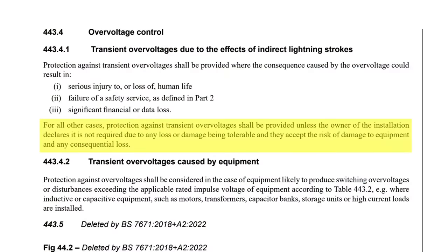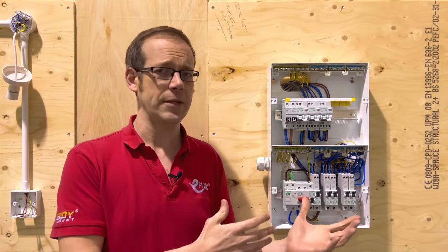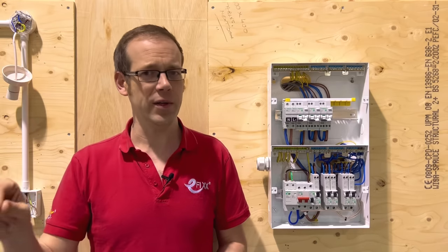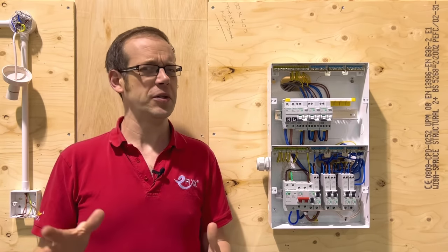For all other cases, protection against transient overvoltages shall be provided unless the owner of the installation declares it is not required due to any loss or damage being tolerable and they accept the risk of damage to equipment and any consequential loss. So for some reason, if you're installing a consumer unit into a domestic property where none of the three indents apply, it's now down to the installation owner to decide if they want it or not. That feels a little bit strange to me.